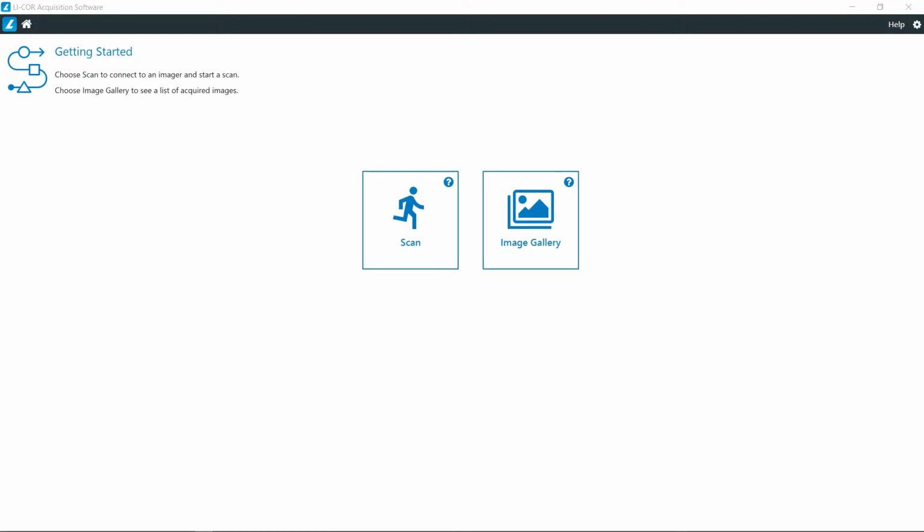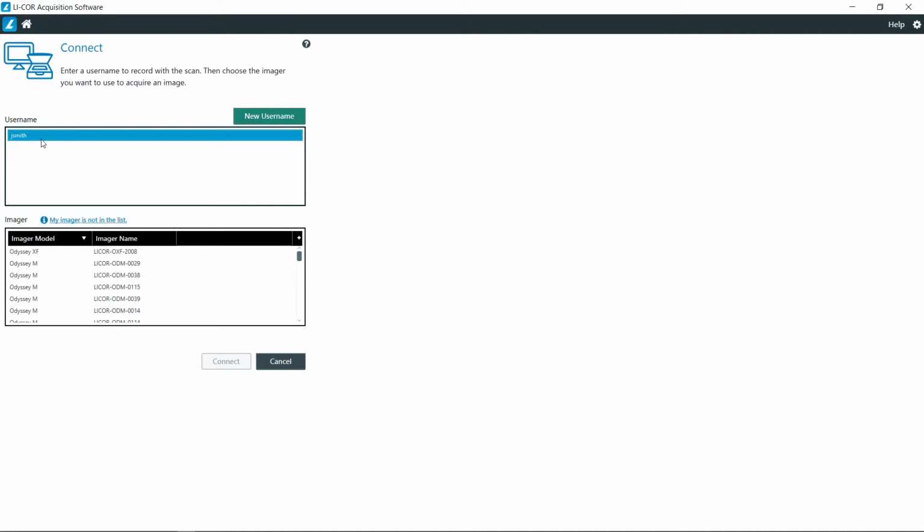In this video, I will be walking you through the steps involved with doing gel acquisitions on the Odyssey M. So with the acquisition software open, go ahead and click on scan, choose your username, and then choose the instrument you want to connect to.